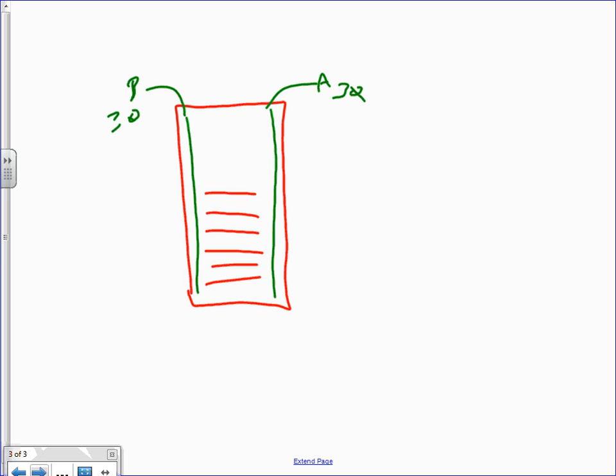A lot of the time the computers only need single phase, just like your laptop. So the plug strips internally are wired so this is phase A, this is phase B, this is phase C, taking the three-phase down into single phase. That's if we have three-phase 4-wire coming in, broken up into phase A, B, and C, so it's 120 volt to each plug on each server. Since they have two plugs, one plugs into this side, one into that side.